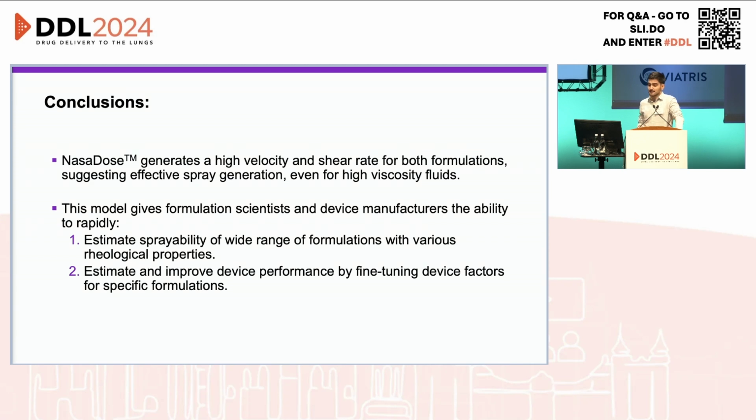It allows us to estimate a wide range of formulations and their sprayability in the NasaDose device. And also, if one specific formulation is all you need, you will be able to fine-tune your device parameters to improve the sprayability of that formulation.